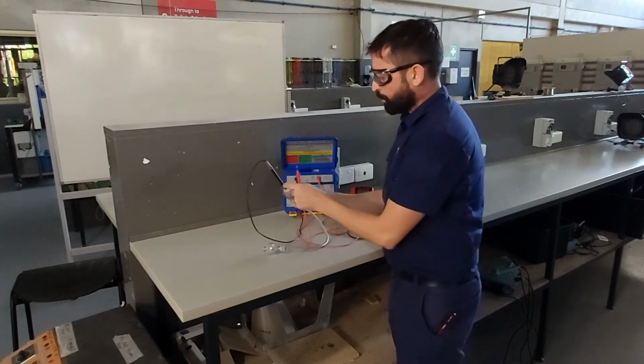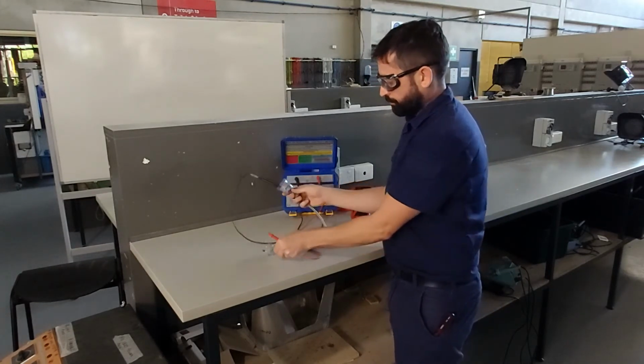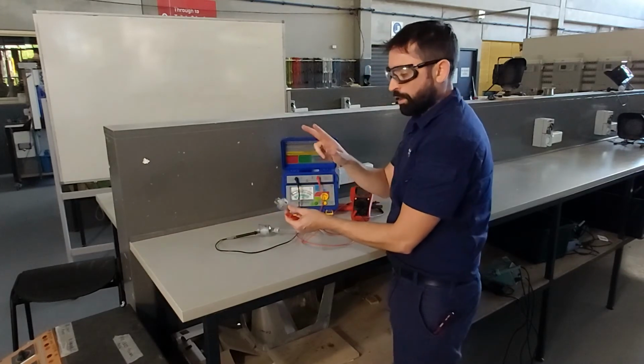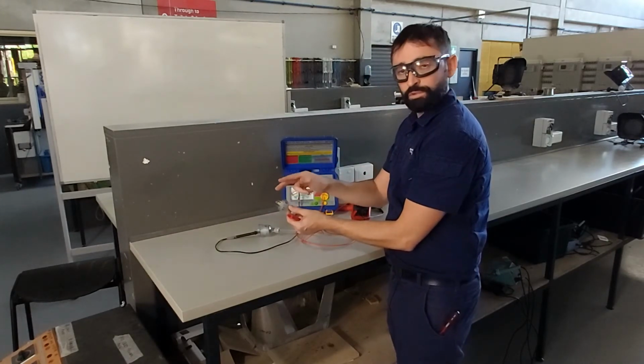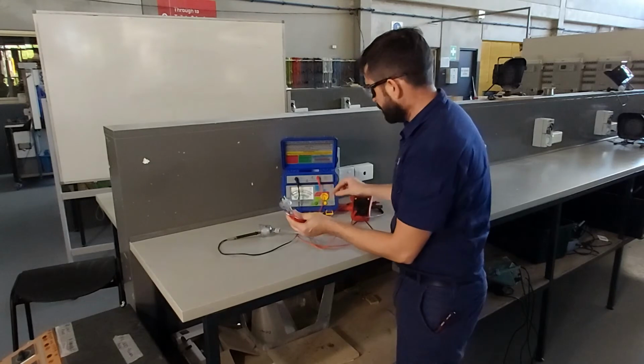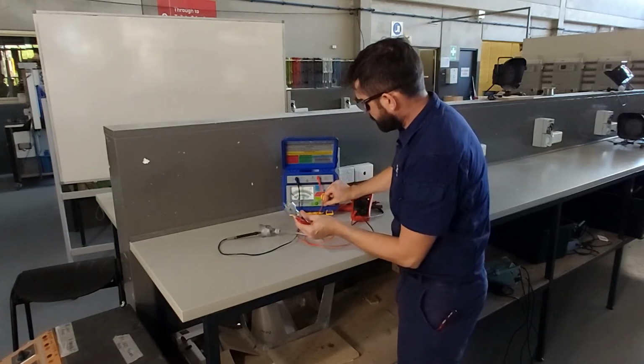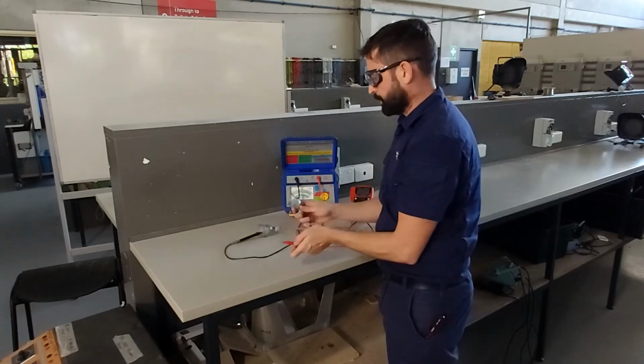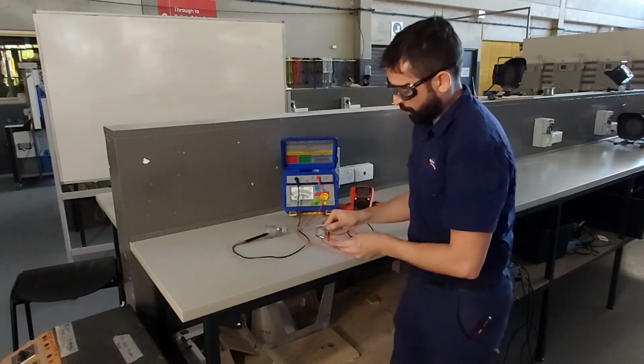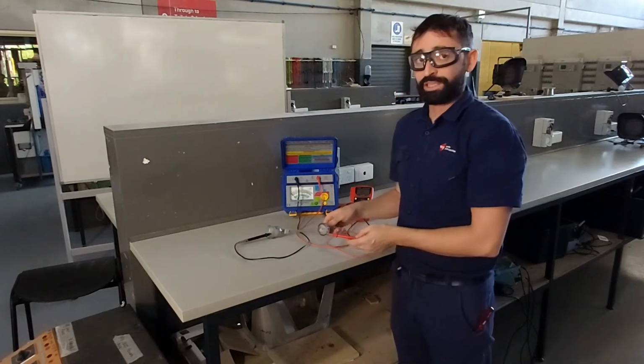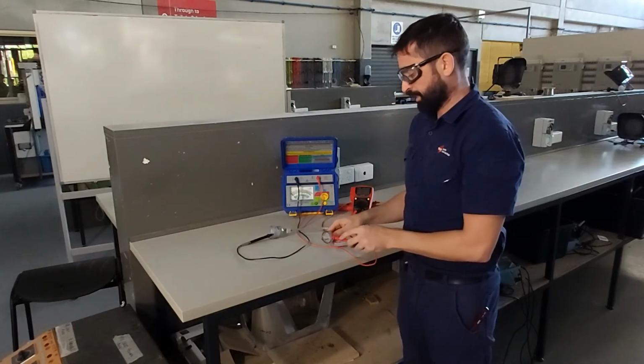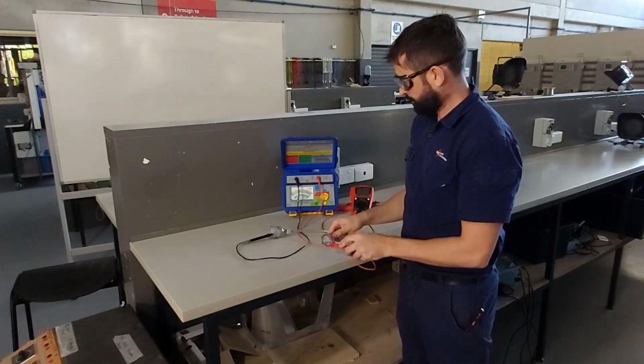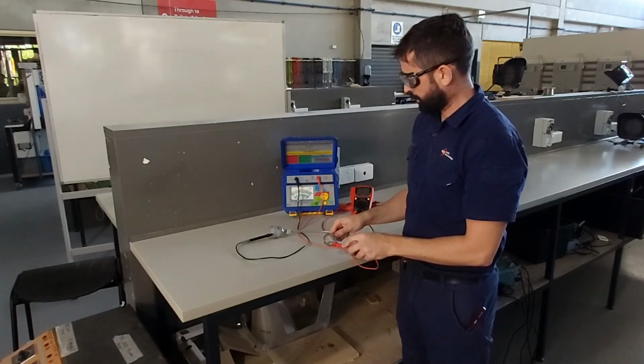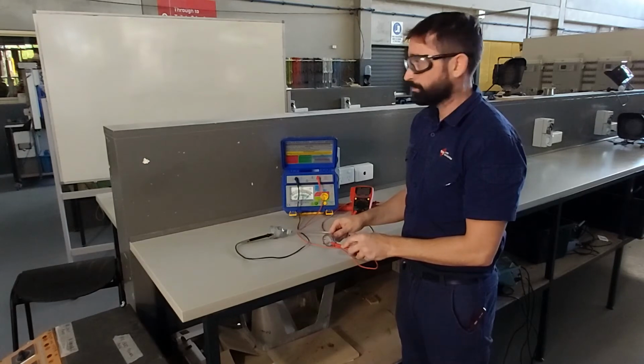So one probe is going down the earth terminal, and we get the other end. So remember, both active conductors. So we're going to do two of them at the same time. Now we need to lock it in place. 500 volts. Now I can touch the earth to make sure that my insulation resistance tester is going to give me a reading that says it fails. Yeah. So you can see the needle on my analog meter, it's gone to 0.